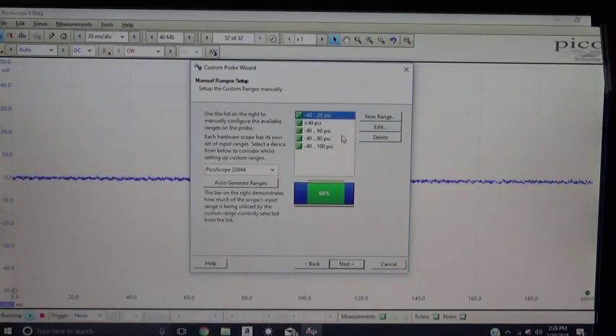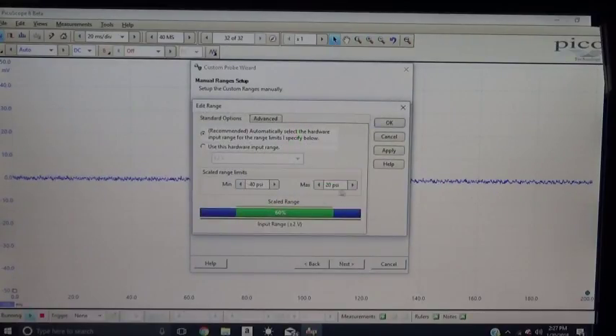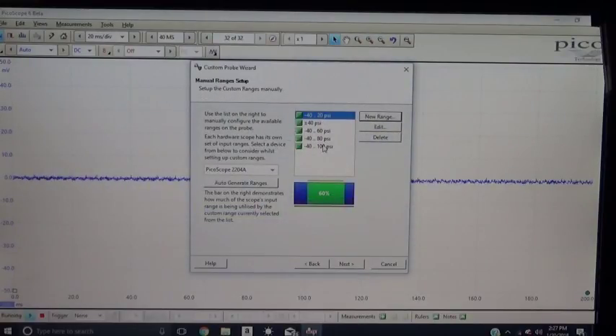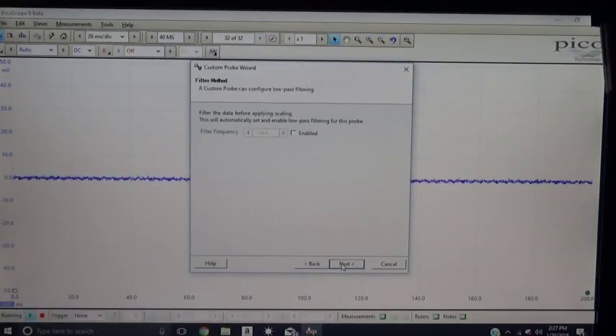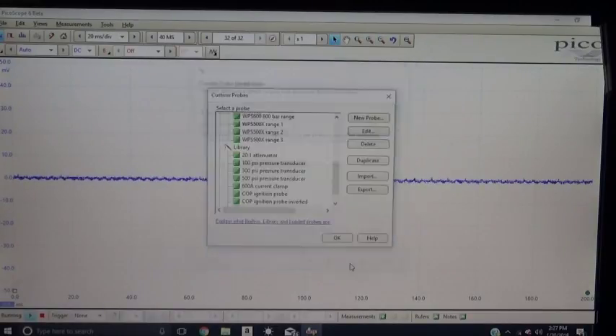Now this is the same as we did on the attenuator, no difference at all. Just click new range if you want to open another. I can go to 100, so this is what you just set your scales here and you're done. It's actually nicer because when you do your measurements, sometimes you want to go up to 60 psi or 80, but the computer's going to mess you up and you won't have your reading right. It'll be okay, but this way you can customize it better so your waveform looks better. So on the 100 psi, I just did 20, 40, 60, 80, 100 psi. It's just your preference, whatever you want to do. So click next again, and we're going to 100 psi pressure transducer, click finish, and you're done with that one.